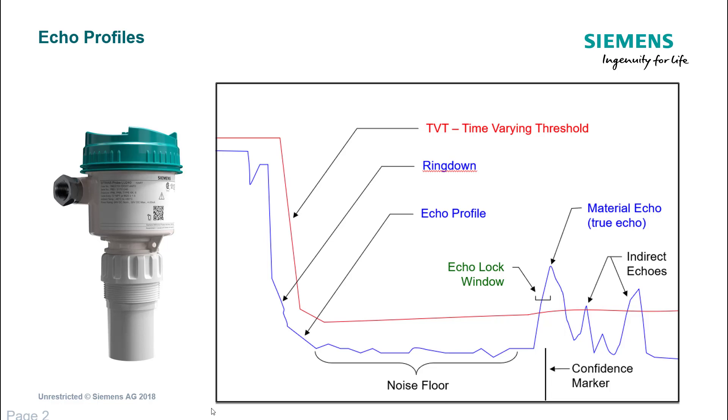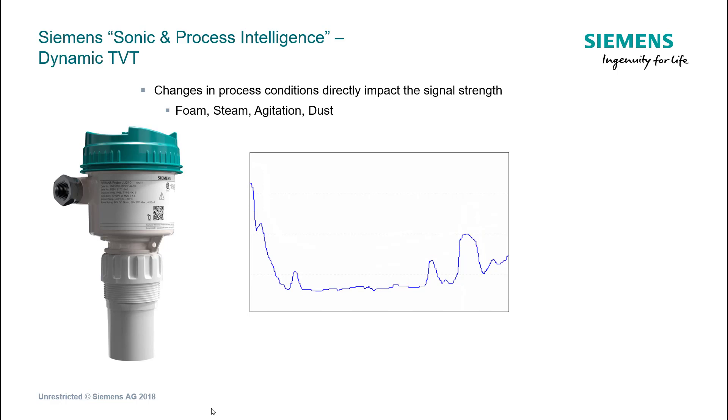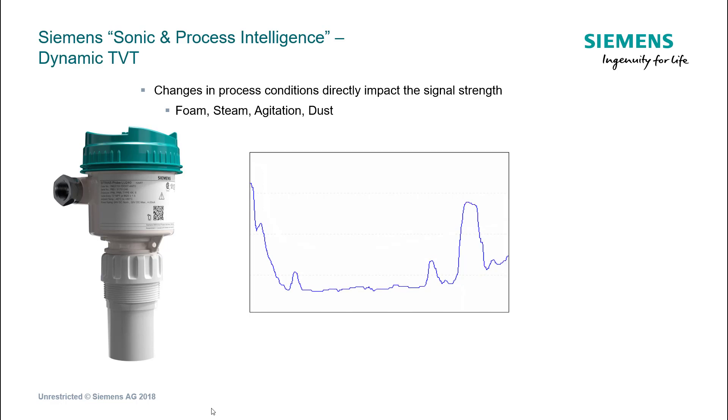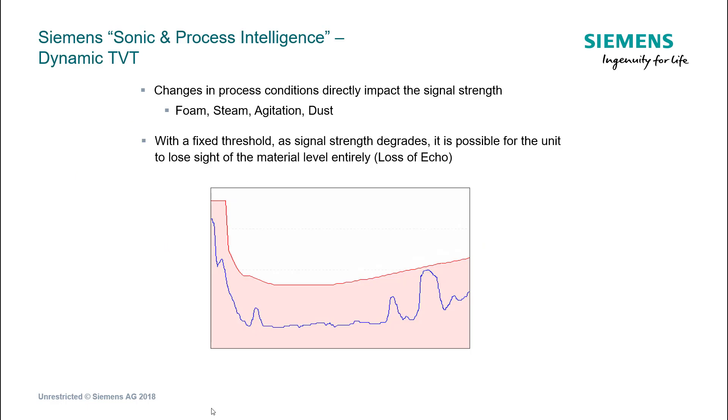Unfortunately, within our process the strength of the signal coming back is not always the same. All technologies are affected by this, some less severe than others. A signal can get attenuated from the actual device aging. Let's look at that trend there. We can see the signals getting smaller, that could be because of dust, steam, foam, whatever.